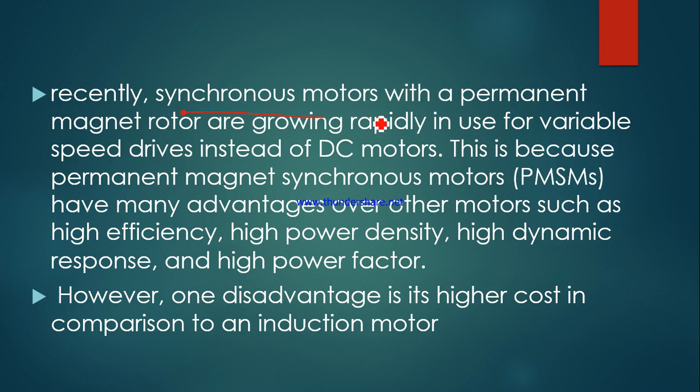Recently, synchronous motors with permanent magnet rotors are growing rapidly in use in variable frequency drives instead of DC motors, because, as I told, DC motors have a lot of disadvantages. Permanent magnet synchronous motors have many advantages over other electrical rotating machines, such as very high efficiency, very good power density, very good high performance dynamic response, and the power factor is drastically improved here.